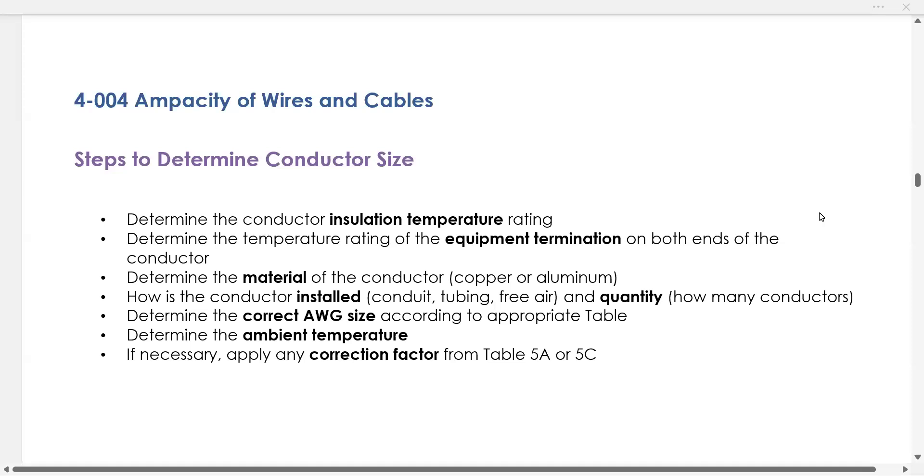So that's all you're doing. You can make a little flow chart of this. You find your insulation temperature rating based on the insulation you want to use. First, you calculate, you make sure that you know the temperature rating of both sides of that cable, of that conductor by knowing your equipment.